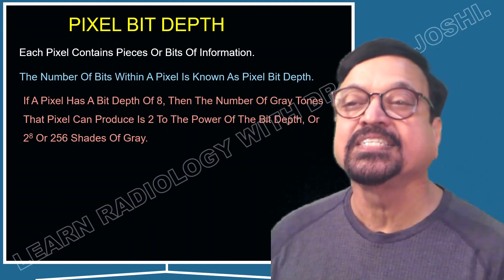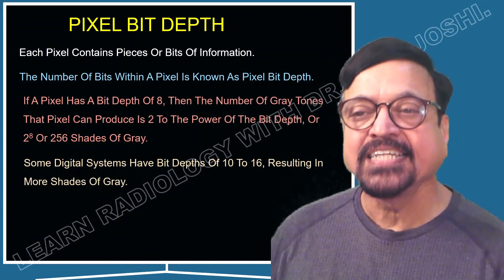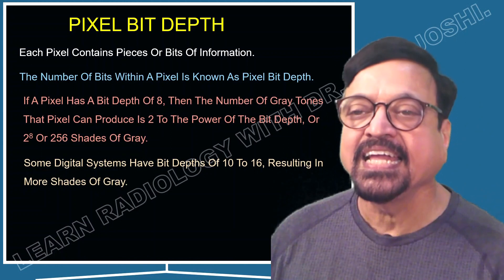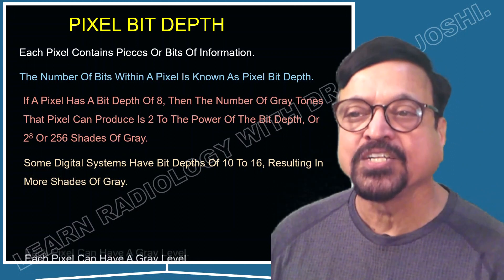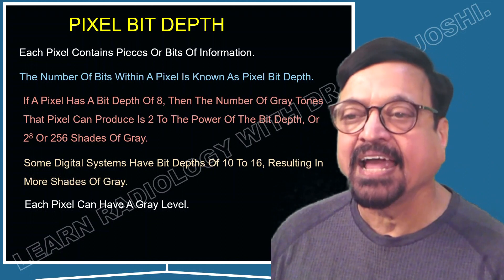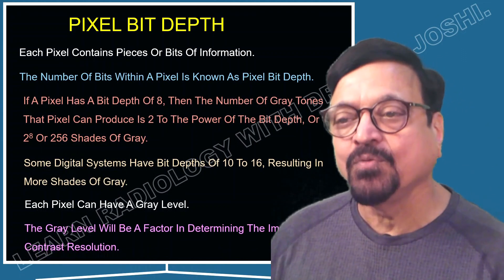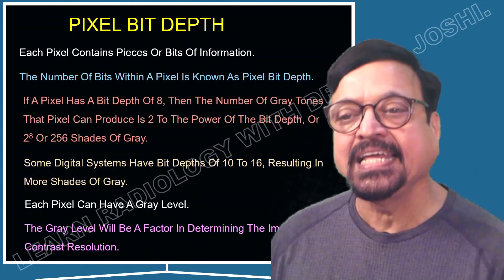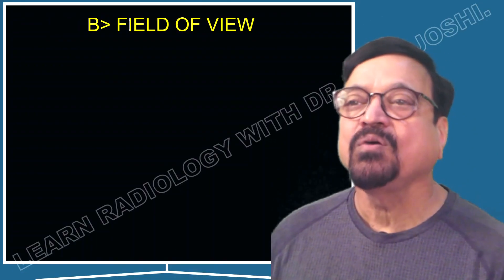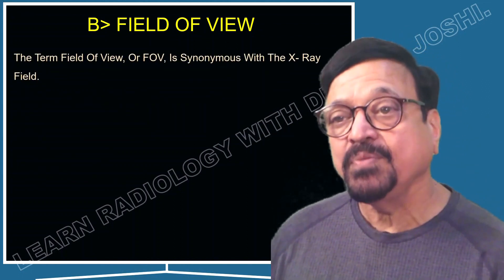That is the routine setting on standard machines. Digital systems with a bit depth of 10 to 16 result in more shades of gray, so better resolution machines are also available. Each pixel can have a gray level, and that gray level is a factor in determining image contrast resolution.